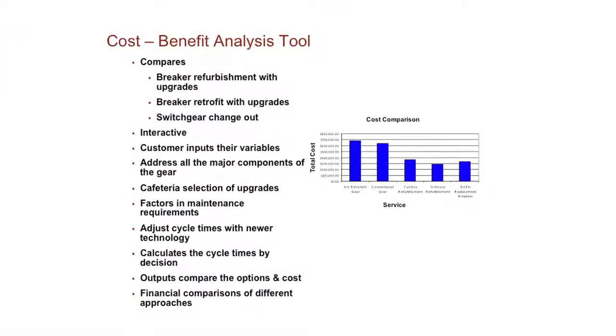We need to understand the factors in maintenance. Are you looking at these breakers once a year? How many hours does it take? Are you spending one hour per breaker per year, or one hour every ten years to look at the breaker? Are you doing refurbishments? Are you doing the refurbishment cycles based on the vendor's recommendations?